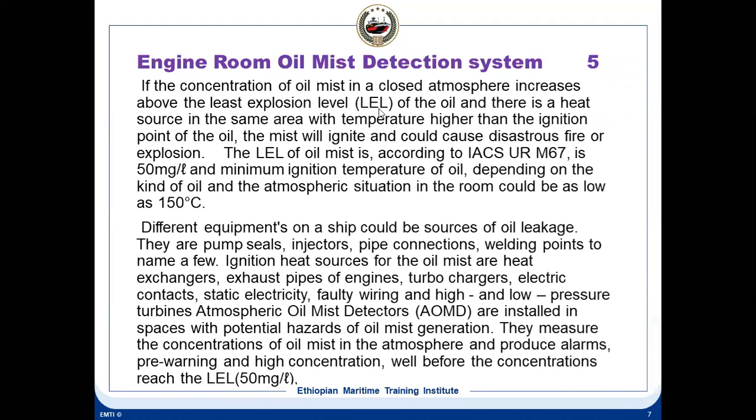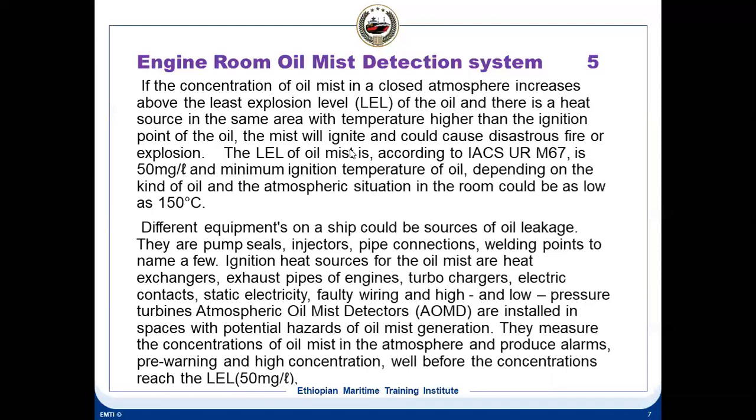So here you can see, if the concentration of the oil mist in a closed atmosphere increases above the LEL, and there is a heat source in the same area with a temperature higher than the ignition point of the oil, it can ignite. Of course, there will be hot pipes and everything. Suppose there is a lube oil pump and there is a leakage of oil, it can cause an oil mist, and there can be some hot surfaces, pipes and all that can cause a fire. So that is why this oil mist detection system is an entirely different system.